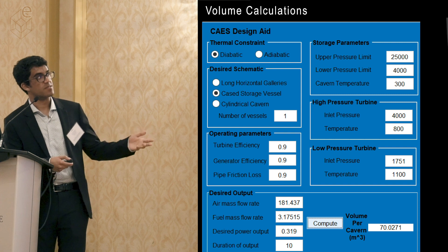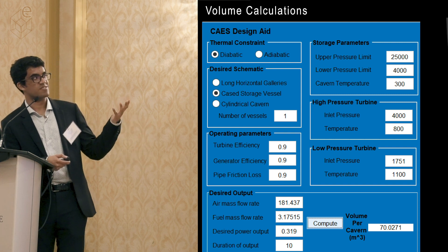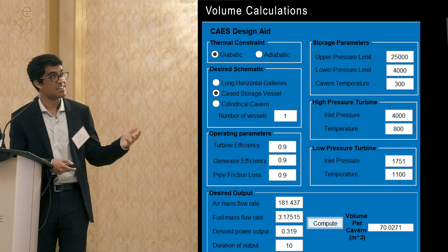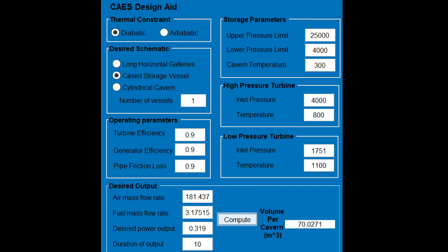The bulk of my research has led me to a volume calculator — and it's funny how four months of research shows up on one slide. This calculator computes a volume for your desired power output in megawatts and duration, giving a megawatt-hour figure. It takes into account thermal constraints — diabatic versus adiabatic — the desired cavern schematic (horizontal gallery, vertical cylindrical cavern, or storage vessel), upper and lower pressure limits, temperature, and turbine efficiencies, producing the required volume.